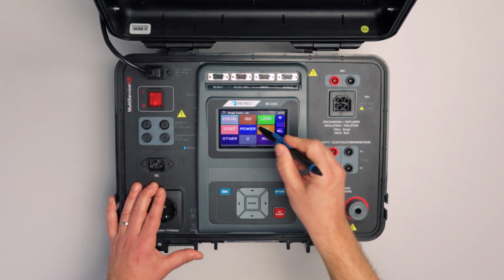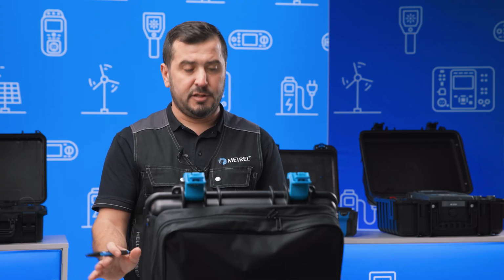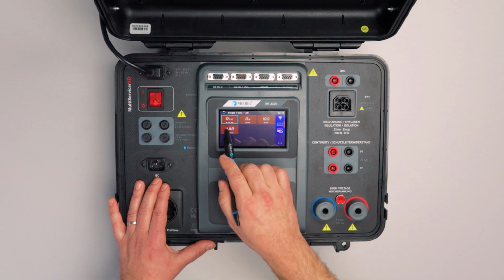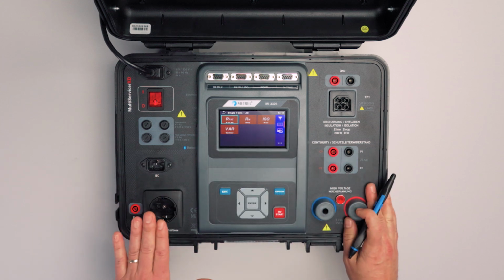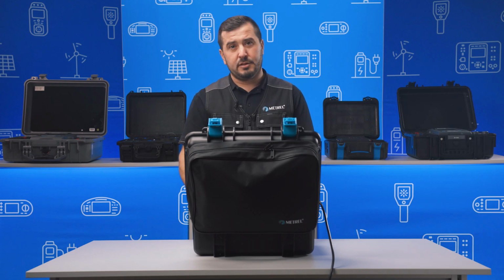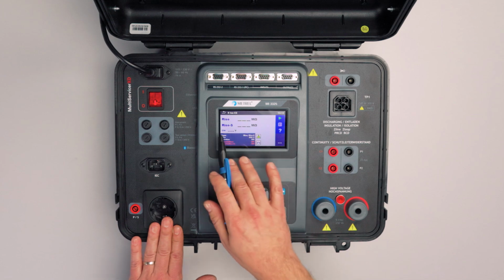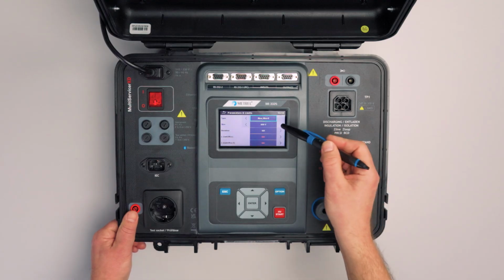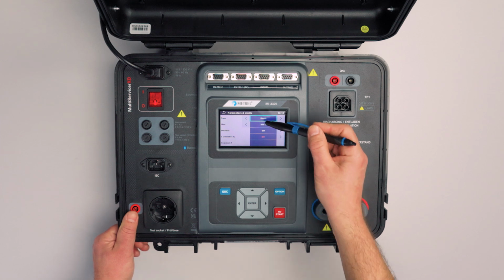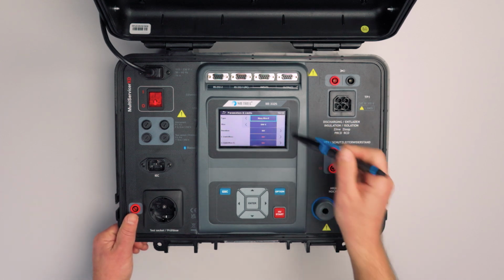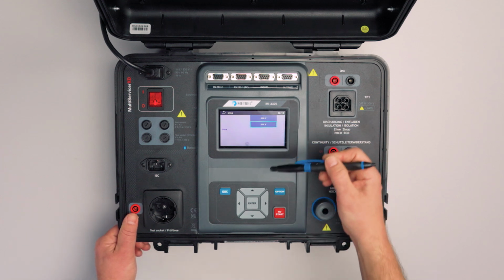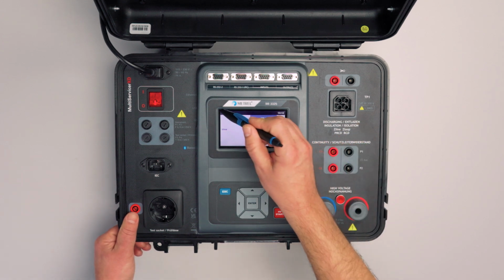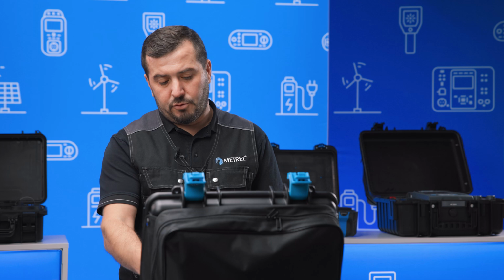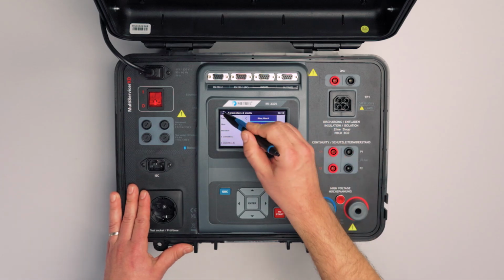The next group inside the single test is the insulation resistance testing group, where we have different options. The first one, called RISO, AA, stands for electrical equipment. If we select this one, the insulation resistance test will be executed via this main test socket, or, in case we are performing it with the probe, then again via this main test socket against the probe. We can always decide whether to measure insulation resistance only for class 2 appliances or for class 1, or a combination of this test. We can also choose between test voltages of 250 and 500 volts. The instrument also supports, of course, setting of duration and the limits.